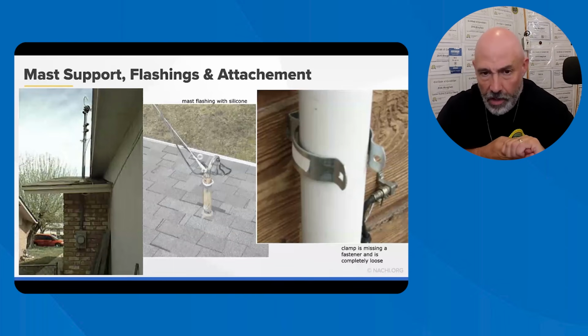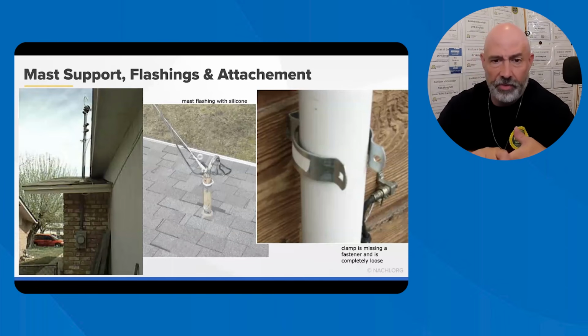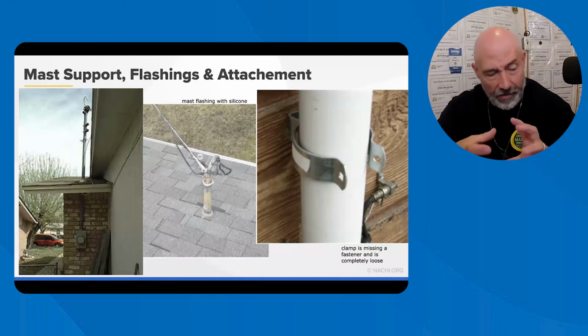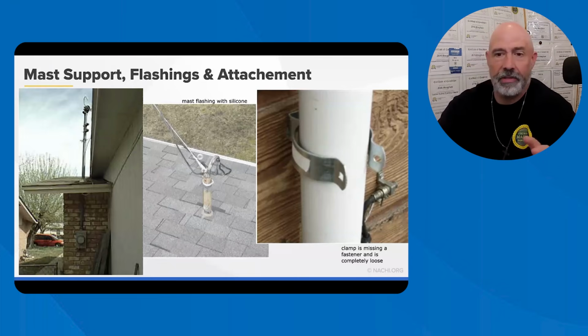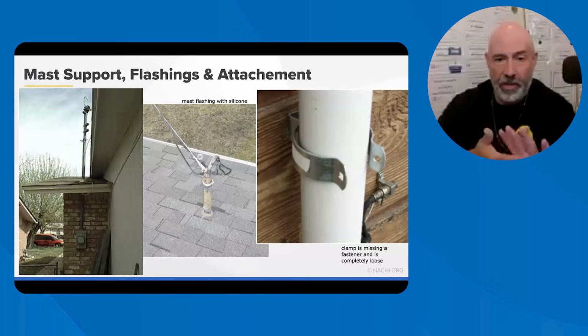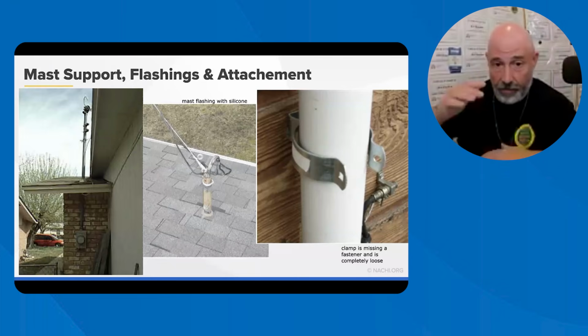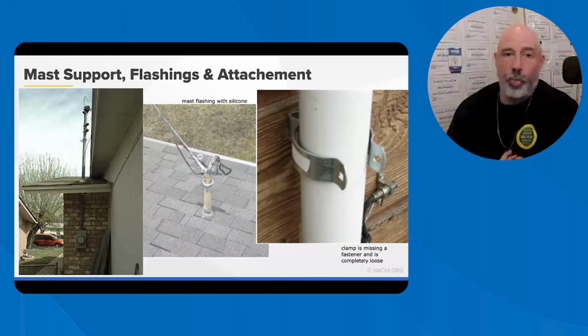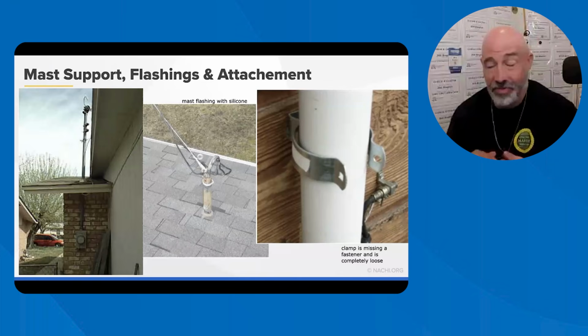But the service mast attachment, you want to make sure that the mast is clamped within like 12 inches of either side of the meter base, as well as the top of the mast too. You want it on both sides. It is way too common to see the attachment clamps not replaced when they're rusted out. I've called that out a bunch of times.